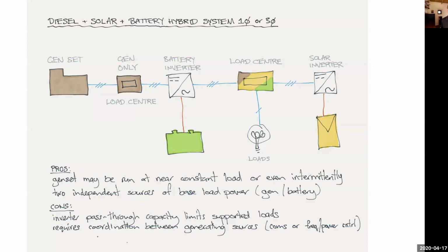I did have a slide here with the pros and cons, which I've just gone through, I think. An important pro, which I forgot to mention, was that one of the big advantages of adding a battery inverter system to a generating set is that suddenly that generating set can be controlled at its optimum efficiency in terms of its demand. Diesel generators, particularly larger ones, like a fairly constant load. You don't want to run a 25 kVA generator at 1 kVA. It's just going to glaze the bores, and it will use fuel very inefficiently. Many generators use almost the same amount of fuel no matter what load you've got on them. So you'll be wasting fuel.